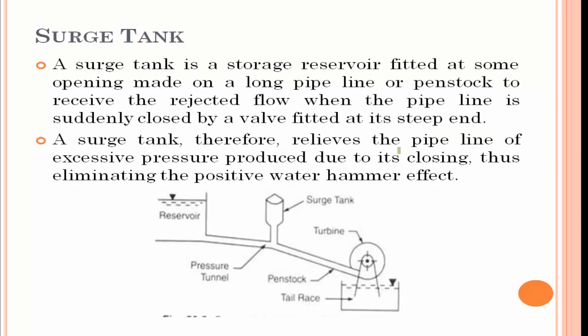Next is the surge tank, one of the important components of the Hydel Power Plant. A surge tank is a storage reservoir. When there is a higher amount of fluid flowing, that may lead to breakage of the turbine, because there is enough pressure and force to break the turbine blades. This is why we use a surge tank. When the water is flowing at a very high rate, it will fill the surge tank so that the water flow will be maintained uniformly. If there is a lower water flow rate, the surge tank will supply water, again maintaining a uniform flow rate.